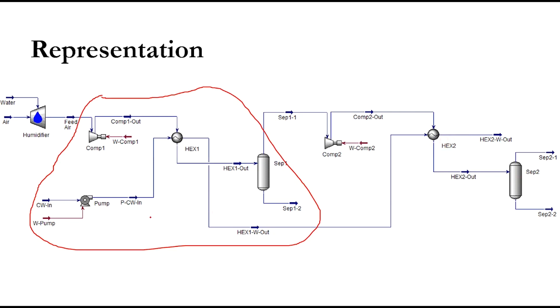The first stage of the compressor includes compressor number one, a heat exchanger, and a separator. The pump is excluded from this stage count as it is for providing cooling water to the coolers. The first heat exchanger is the interstage cooler and the second is the after-stage cooler for the two-stage system. If there are three stages, there will be two intercoolers and one after-cooler.